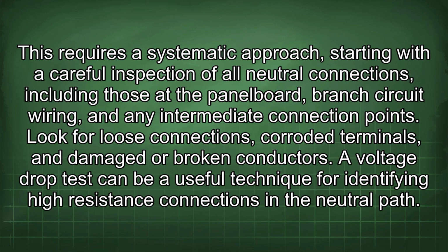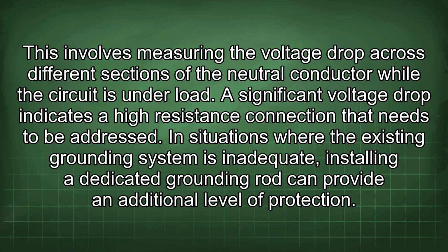This requires a systematic approach, starting with a careful inspection of all neutral connections, including those at the panel board, branch circuit wiring, and any intermediate connection points. Look for loose connections, corroded terminals, and damaged or broken conductors. A voltage drop test can be a useful technique for identifying high resistance connections in a neutral path. This involves measuring the voltage drop across different sections of the neutral conductor while the circuit is under load. A significant voltage drop indicates a high resistance connection that needs to be addressed.